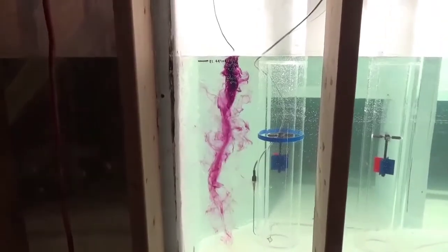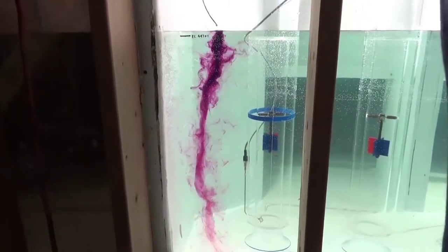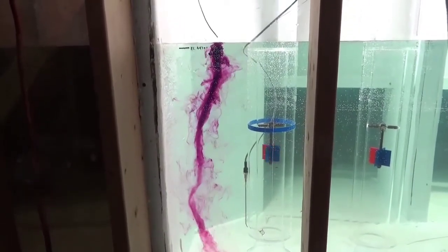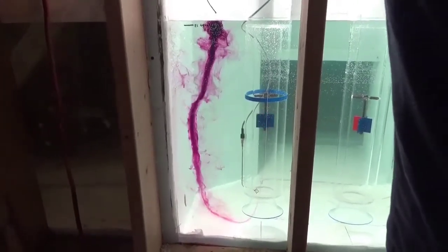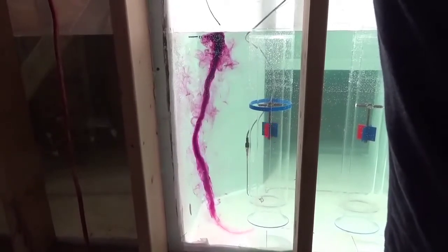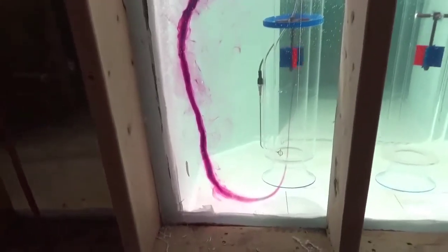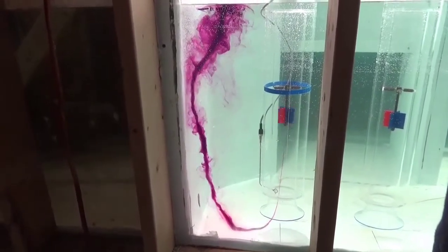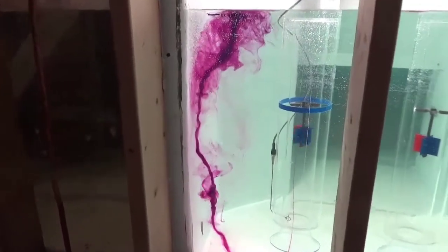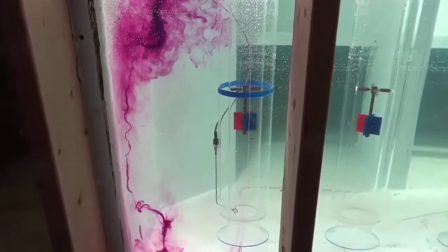All right, so we're going to watch one more form here. You see that ribbon just starting to go down. It's a type 2. It's just organizing into a type 3. You see it just going to get in. This one's going to make it down into the pump. There we go. Now it's going to tighten up a little bit, and you'll see that core reach all the way down in. And now that core is making it all the way up through, actually to the impeller location right here. You can see that. So they're not real frequent, and that looks bad. It's not a real strong one. The flow conditioning basket will chop that right up and dissipate it without any problem at all.